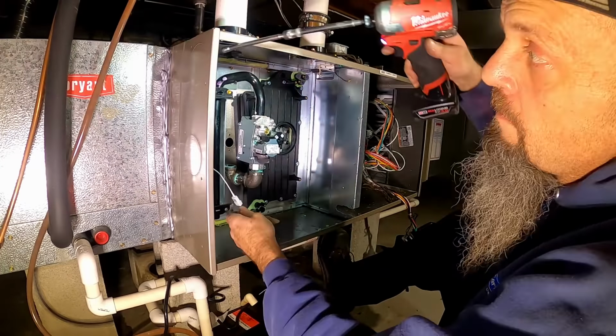And the only reason why I changed that secondary out was the screws for the collector box were stripped. When I first went out there, I couldn't get any grip. It wouldn't pull in. It just sucks. There's nothing you can do. And as you've seen, I was tightening up that center screw, and that center screw just freaking stripped.